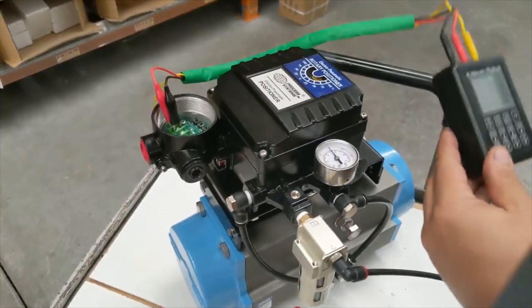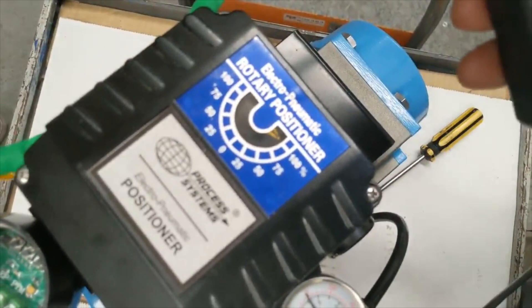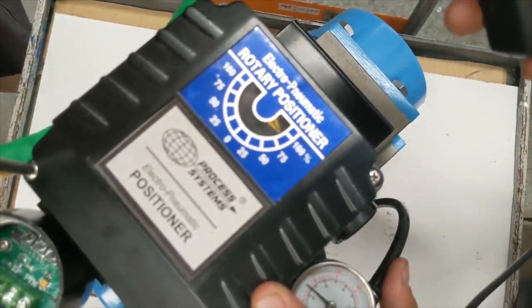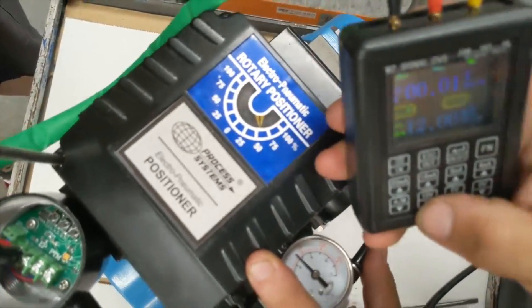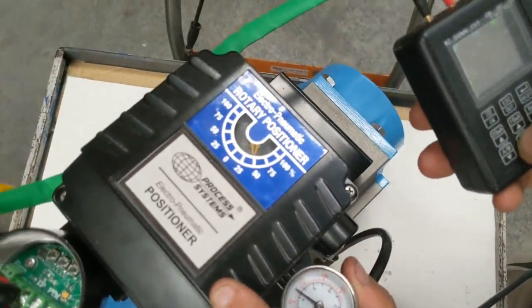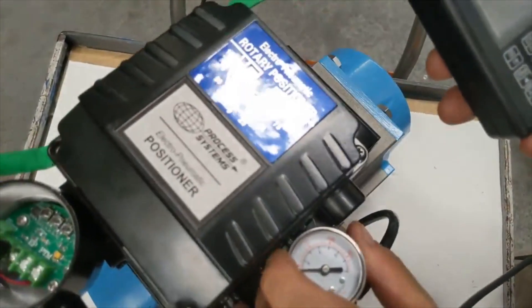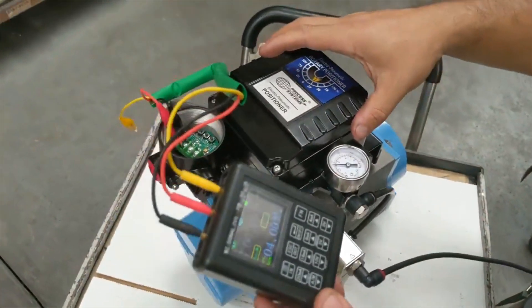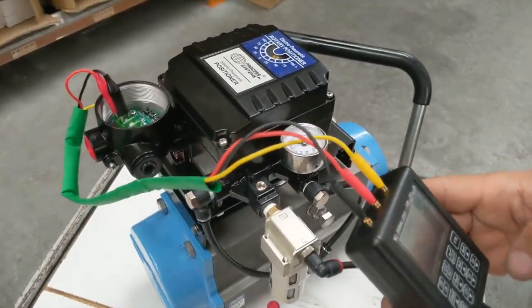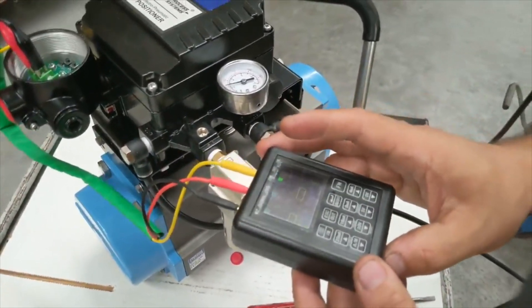Another way to show you is through the indicator on the lid: 20 milliamp shows 100 percent, 12 milliamp shows 50 percent, and 4 milliamp is zero percent. When you lose signal the valve will return to its zero percent if it's not at that position already.